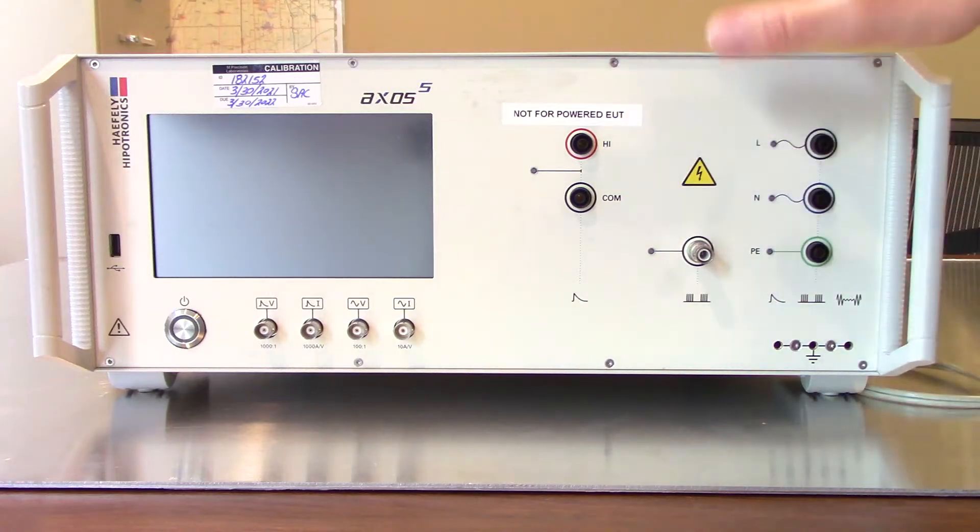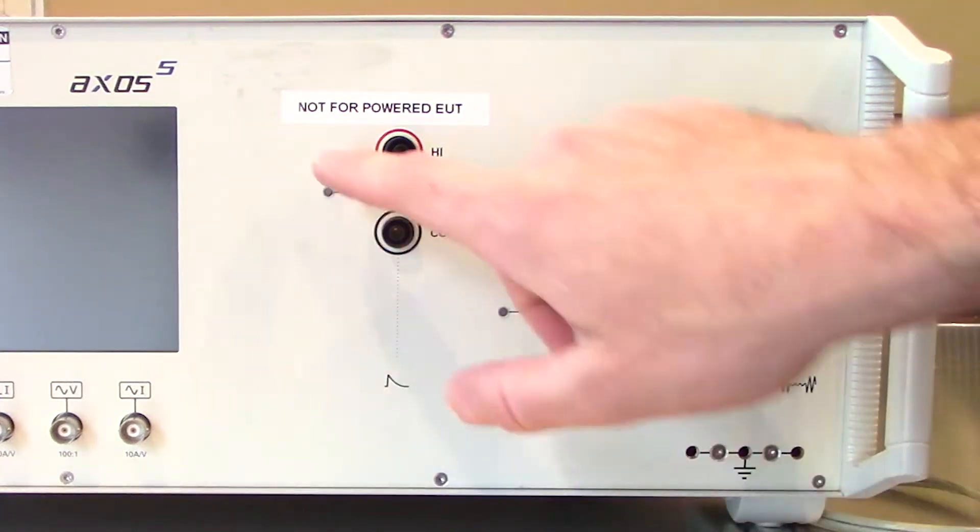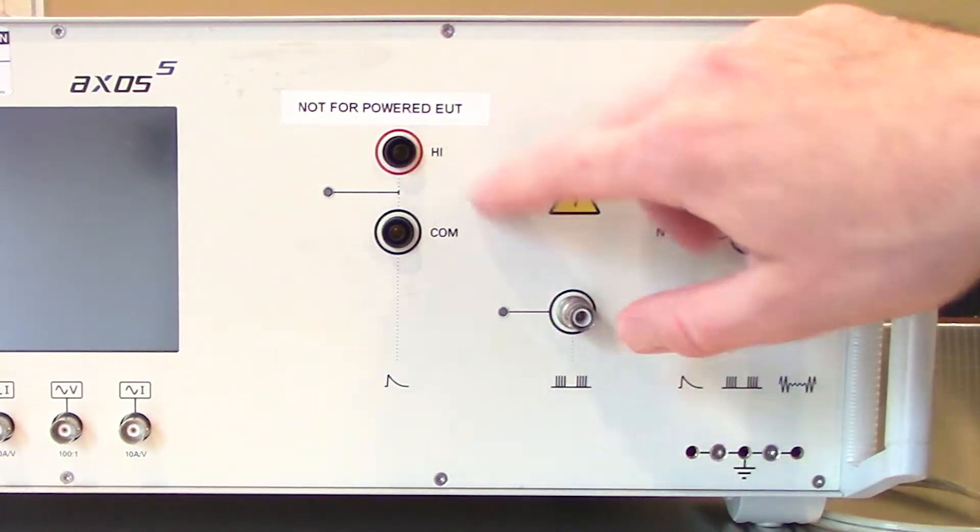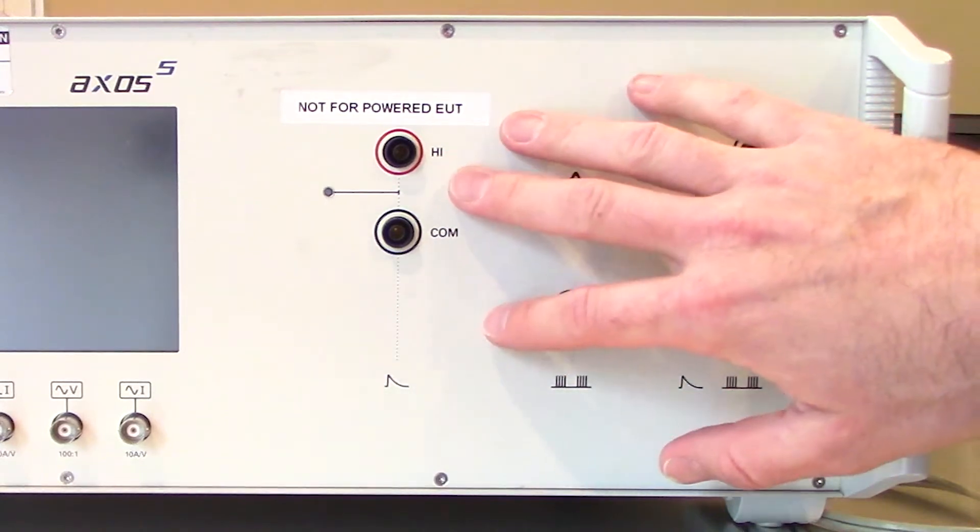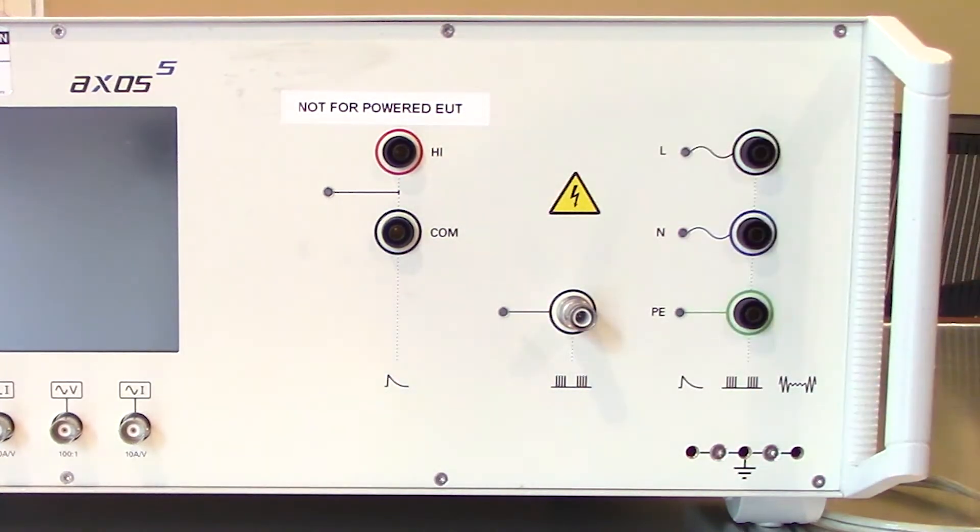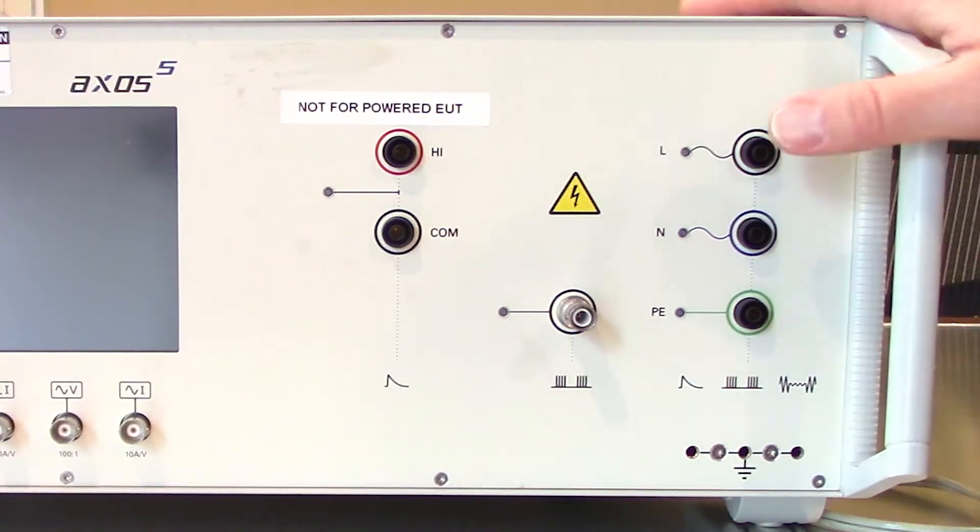Taking the front side of your Haefely Axos 5, you'll see your direct out for combination wave surges and an icon here as well as a note saying not for powered equipment under test. So just be sure, like we're going to do in this video today, if you're doing power on testing you are going through the connections here on the right, which is going through your coupling decoupling network.